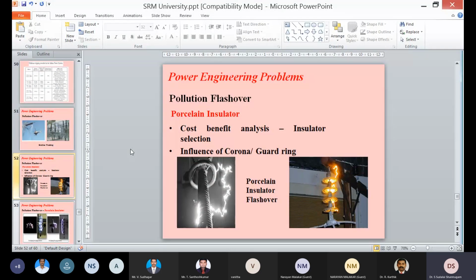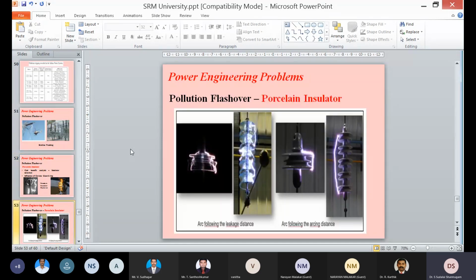And over 100 years, we have been traditionally using porcelain insulators and glass insulators in the Indian power system. However, because of this pollution problem, we started moving more and more towards polymeric insulators. This polymeric insulator is of course made up of organic material. Any organic material will be subjected to thermal degradation and UV degradation. Therefore, the corona ring and the voltage distribution, all other things come into a very unique picture.